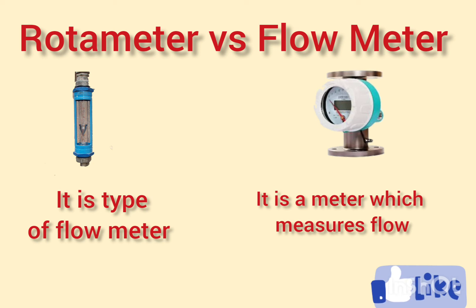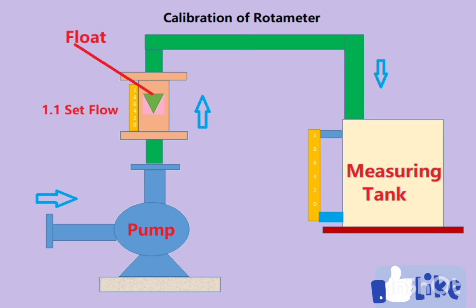This is the setup for calibration of rotameter. You can use any kind of pump - maybe a centrifugal pump or another kind of pump. We install the rotameter we want to calibrate on the discharge side of the pump, and we need a measuring tank to measure the amount of flow coming in.